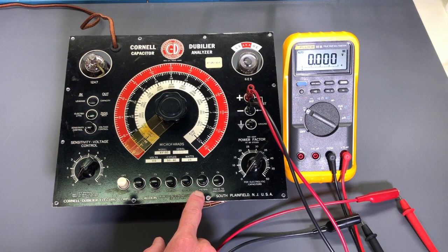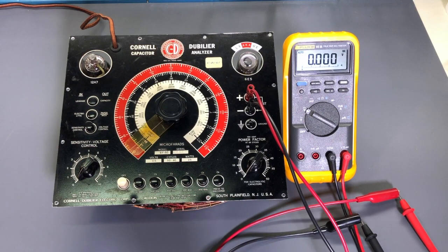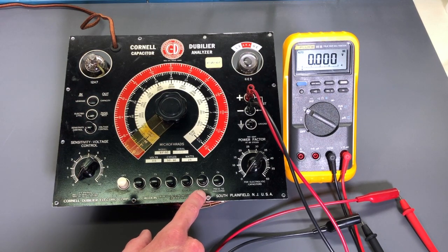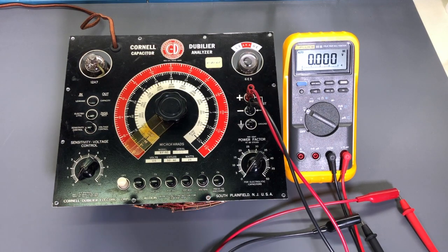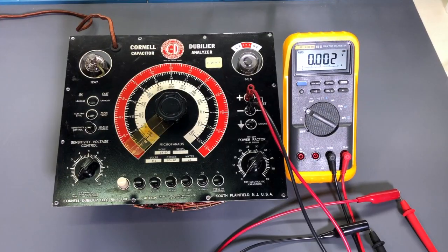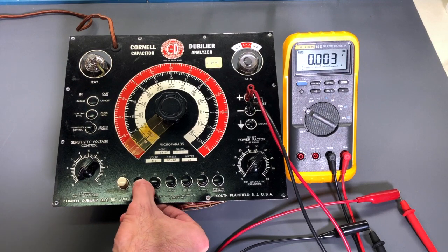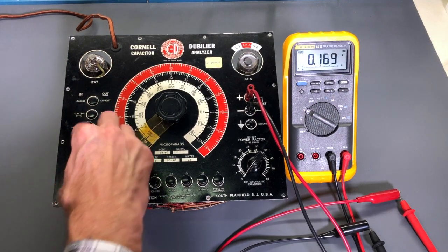Again, this 400 to 600 range, the tester does not actually put out up to 600 volts. I believe it stops around 450 volts, so we wouldn't expect this to go all the way to 600. That is mentioned in the manual about the limit stopping around 450 volts and not going to 600 volts. All right, I'll turn the tester on and we'll see if the voltage ranges look like they're working correctly.